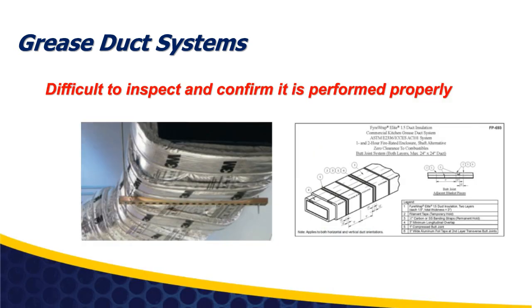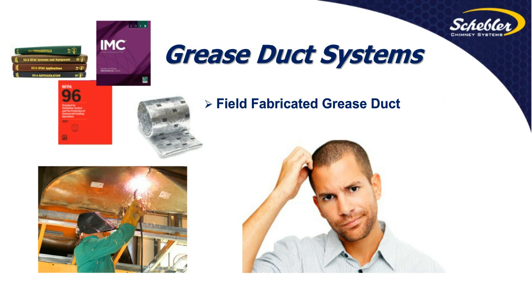The difficult thing is that since there is no one single definitive guideline for any of this, no single guideline for construction, no single guideline for installation, it becomes really difficult for anybody to automatically walk onto a job site and ensure that the ductwork is constructed within the confines or the thought of the code. And there are going to be a lot of areas where ductwork is really hard to inspect because you're inspecting everything in place up in the air, and it's really difficult to go back and redo some installation once it's all assembled. So the real question to me with field fabricated is how confident can you be that all the critical steps have been taken in the construction and installation to make sure that I'm getting the fire protection that the installation was originally tested to.